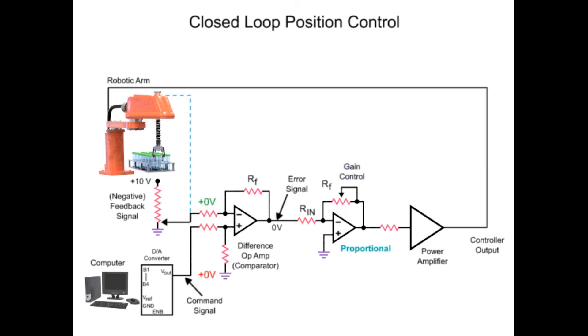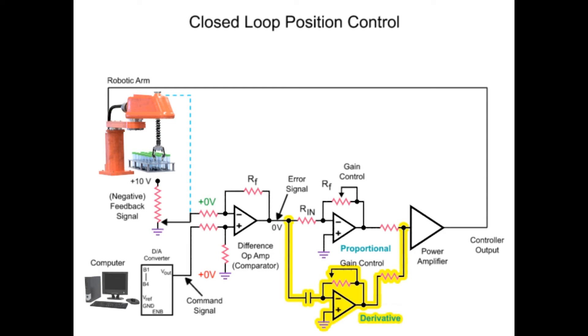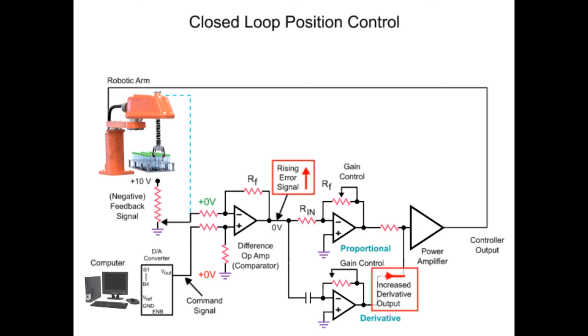To achieve a fast response time and minimize overshoot of the desired position, a derivative amplifier is added to the circuit. The derivative amplifier produces an output while the signal applied to its input is changing. As the arm lags behind the command signal, the error signal causes the derivative amplifier to produce a voltage that adds to the output of the proportional amplifier. The sum of both voltages is applied to the power amp, causing the robotic arm to accelerate at a similar rate to the changing command signal.